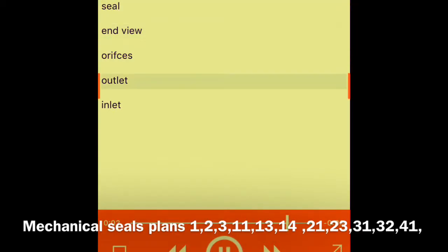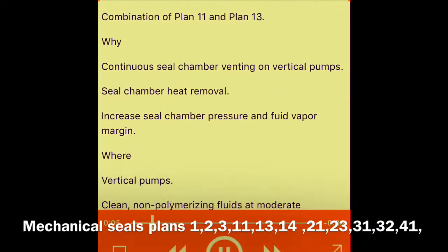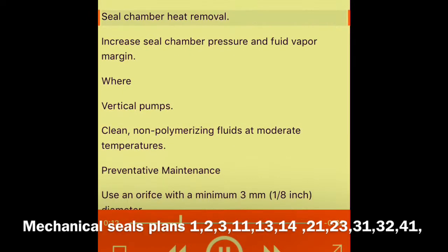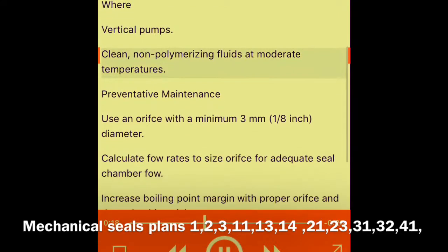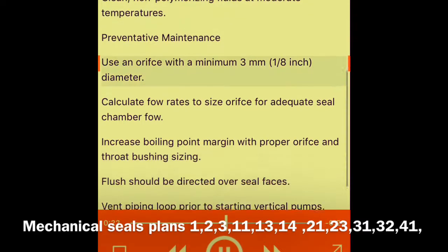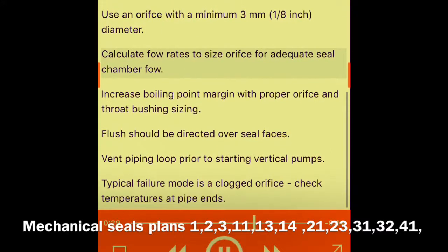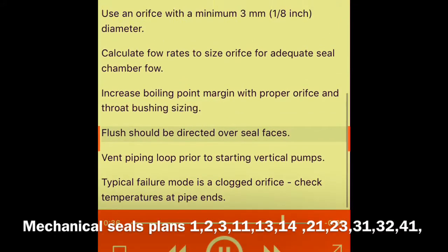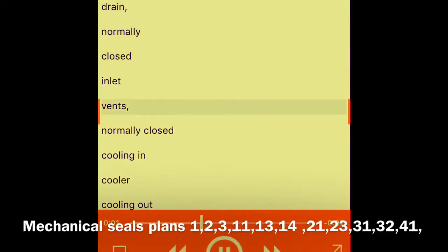Plan 14 — seal end view, outlet and inlet orifices. What: seal flush from pump discharge and recirculation to pump suction with orifices. Combination of Plan 11 and Plan 13. Why: continuous seal chamber venting on vertical pumps, seal chamber heat removal, increase seal chamber pressure and fluid vapor margin. Where: vertical pumps; clean, non-polymerizing fluids at moderate temperatures. Preventative maintenance: use inlet orifice with a minimum 3 mm (1/8 inch) diameter; calculate flow rates to size orifice for adequate seal chamber flow; increase boiling point margin with proper orifice and throat bushing sizing; flush should be directed over seal faces; vent piping loop prior to starting vertical pumps. Typical failure mode is a clogged orifice. Check temperatures at pipe ends.